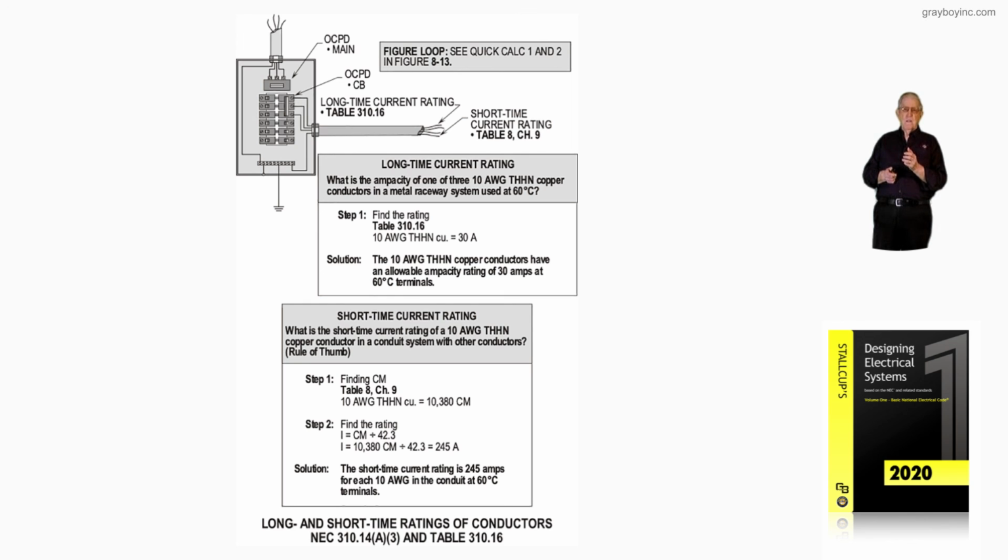So we know then that the 20 amp overcurrent device on the number 12 wire is good really for 24 amps, so the code is satisfied, and section 310.15(C) is satisfied where we had 4 or more current carrying conductors. And our figure 8-13 illustrates this. So keep this in mind when you're dealing with current carrying conductors in a raceway, and you sure don't want to exceed 9.